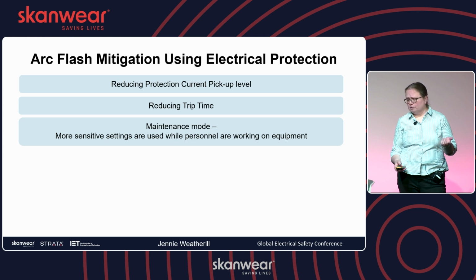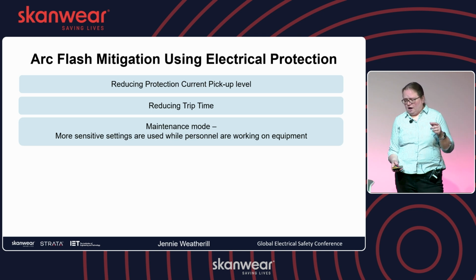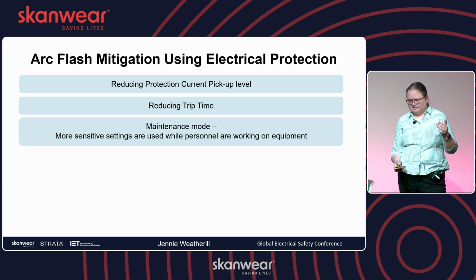Maintenance mode, we've said this, so you can put more sensitive settings in when someone's working on it, but there are some issues on how this is used, because if you're relying on a person to switch it on, is it going to be switched on? So can you link it into when they put it into local? Can you link it to the door opening? Things like this. And then you've also got the issue of putting it back again after they've finished, so that you don't end up with these more sensitive settings in permanently.